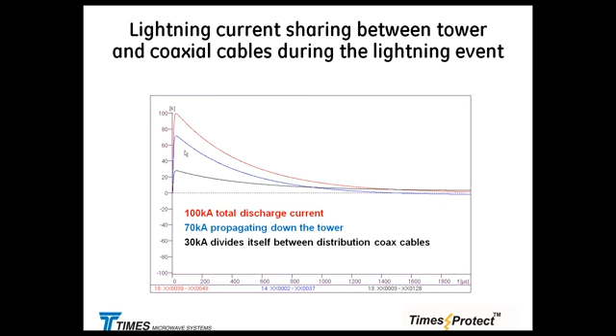Anyway, let's assume a 100 kiloampere strike, which is pretty massive from what you remember of the distribution graph. If 70 kiloamperes goes down the tower, the remaining 30 kiloamperes will divide itself among all the other service cables coming down from the antennas to the shelter. Take a very basic tower, 3 sectors, 2 antennas per sector, 6 cables total. Dividing the 30 kA among the 6 cables, you're looking at around 5 kiloamperes per cable. Let's remember that 60 to 70% of that current will be going on the shield and around 30% on the center pin. So you can figure out quickly how this divides itself.